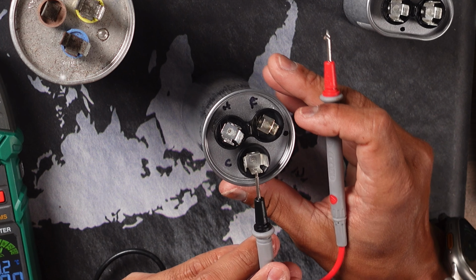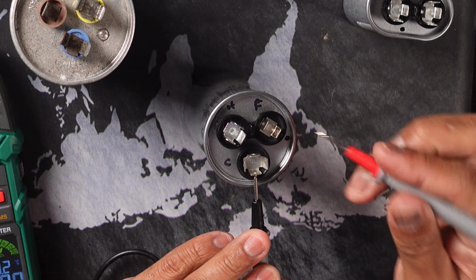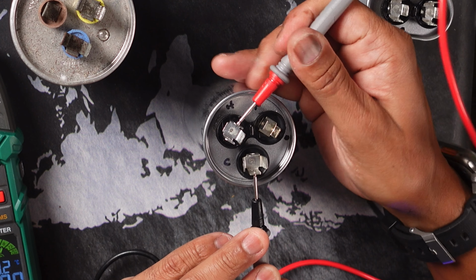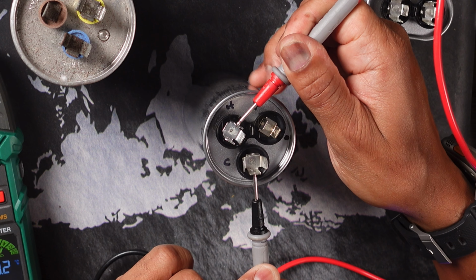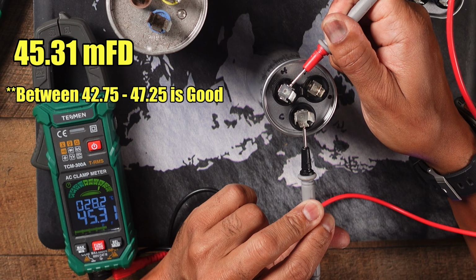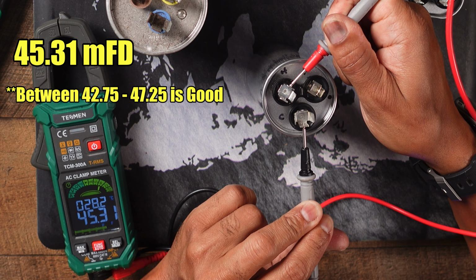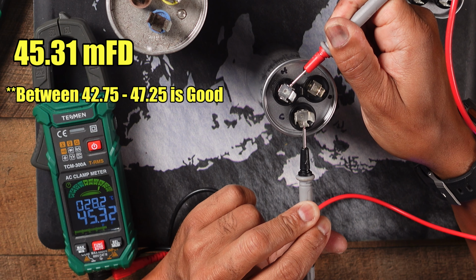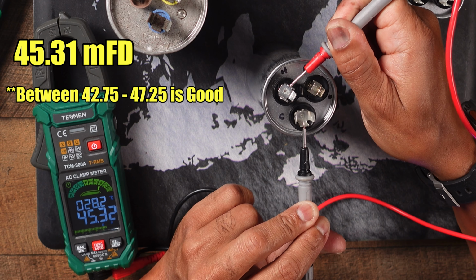To test the other side, do the same thing: put one probe on the C terminal and the other lead on the H terminal. Let it sit and look at that. It's reading 45.31 microfarad, which means this capacitor is good and within the bounds of what it should be.